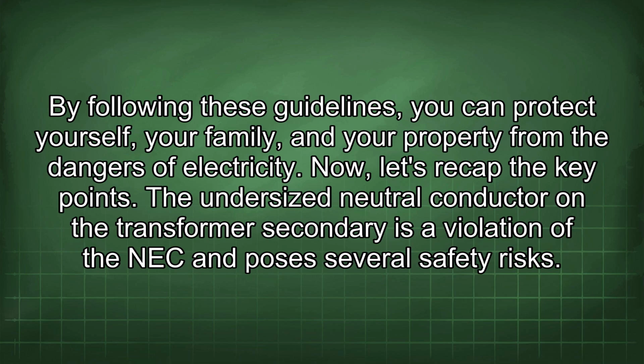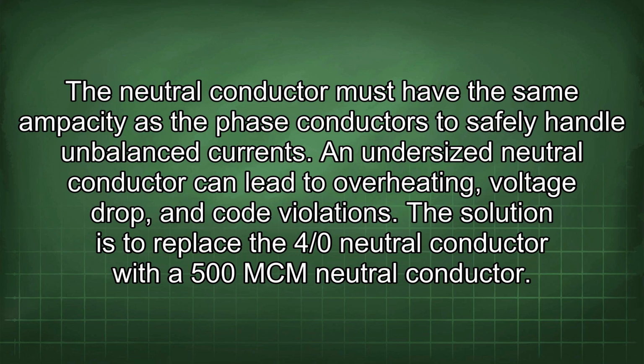Now let's recap the key points. The undersized neutral conductor on the transformer secondary is a violation of the NEC and poses several safety risks. The neutral conductor must have the same ampacity as the phase conductors to safely handle unbalanced currents. An undersized neutral conductor can lead to overheating, voltage drop, and code violations. The solution is to replace the 4/0 neutral conductor with a 500 mcm neutral conductor.